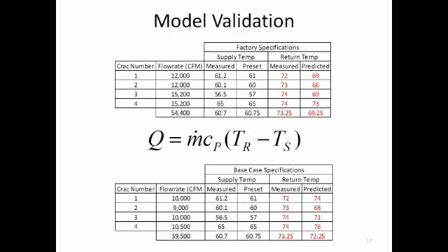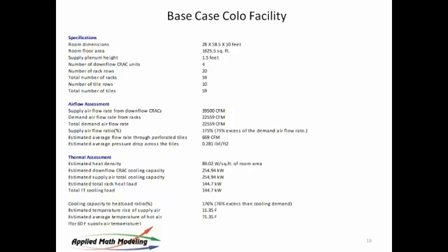Well, yeah, but the other thing too is that it's not a stretch to cut back on the flow rates on some of these CRACs if they're older. That's right. You know, because dust gets in filters and things don't work as efficiently. They're belt drive machines, most of them, not direct. So they don't necessarily work up to the factory specs if they've been in use for 10 or 20 years. That's right. It's not surprising to see a 20 to 30% variance on them. So let's assume that that's okay.